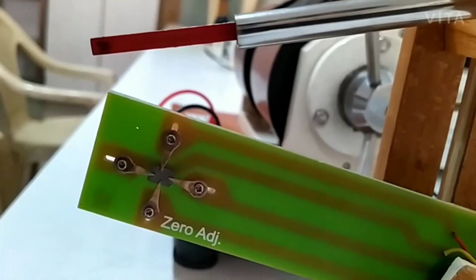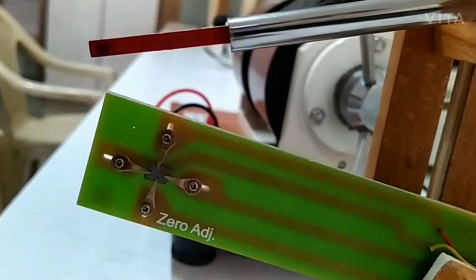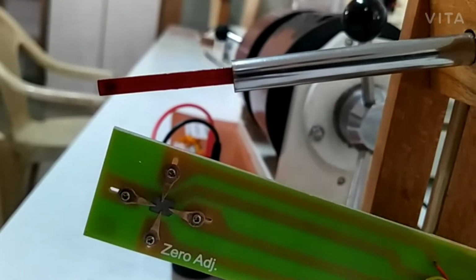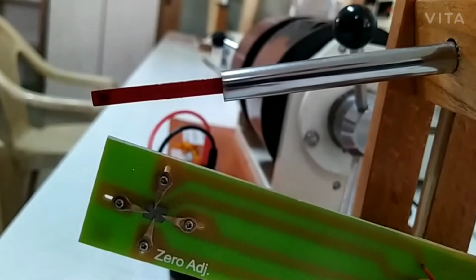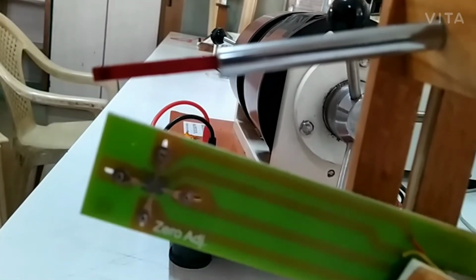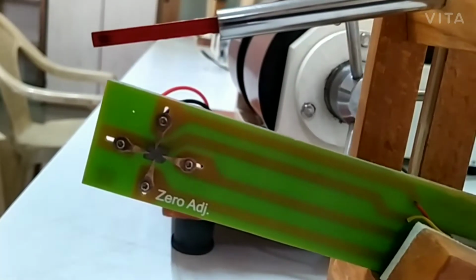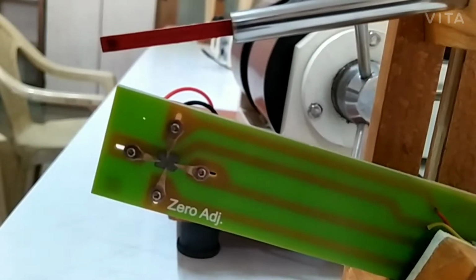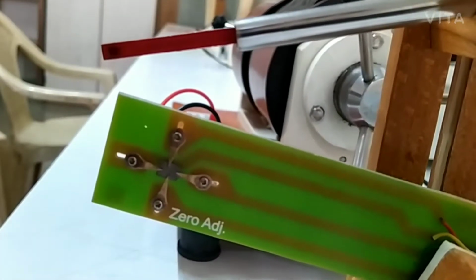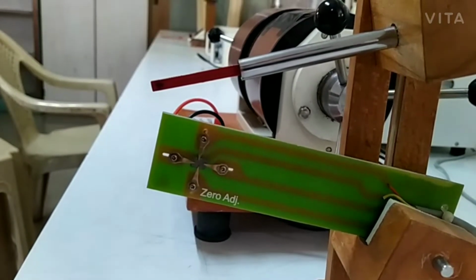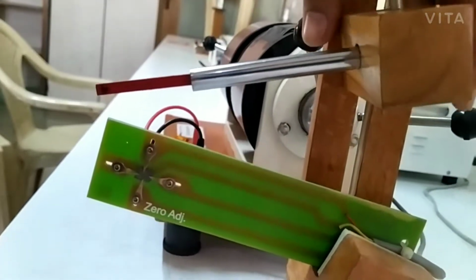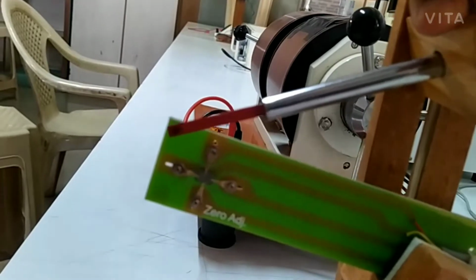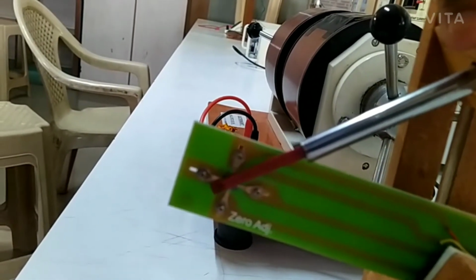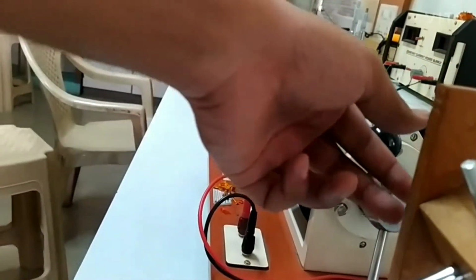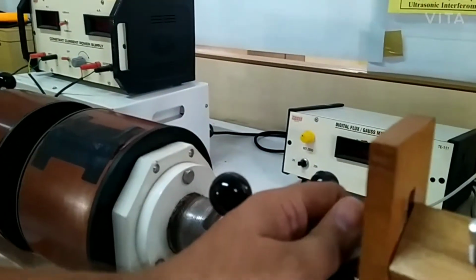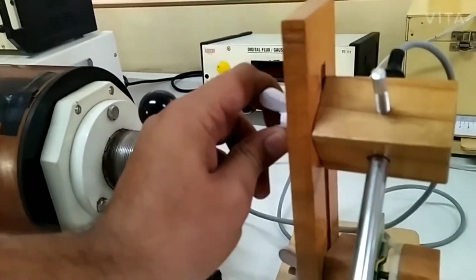our semiconductor sample, which has 4 contact points. The 2 horizontal contact points are used for passing current through it, and the 2 vertical contact points are used for the measurement of voltage across the given sample. While placing the Gauss probe, make sure that you are placing it above your sample and then tighten the knob.